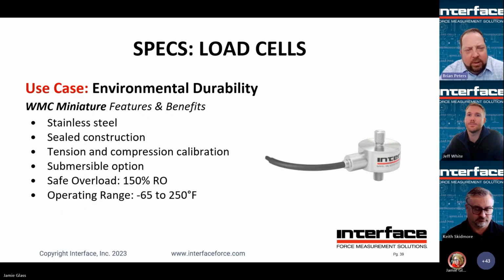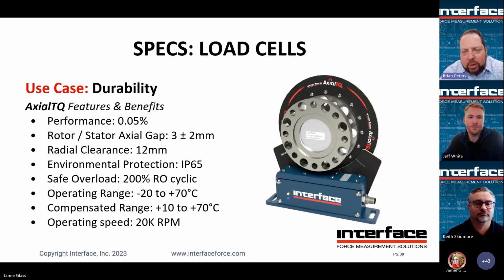Yeah, so there are other rotary torque measurement options. We offer quite a few that have shafts. But again, sorry, if you can go back real quick. From a durability standpoint, this lends itself really well. These are some of the specifications that you'd want to zoom in on when you're selecting a sensor for durable torque testing. Essentially, this is a separate rotor stator assembly, so there are no rotating parts to wear out, no bearings to wear out. It also has pretty high overload, which I think we forgot to put in. Oh yeah, there's 200%. So much higher safe overload in terms of being able to handle a shock or some inertial issues, which sometimes pop up in rotary torque.